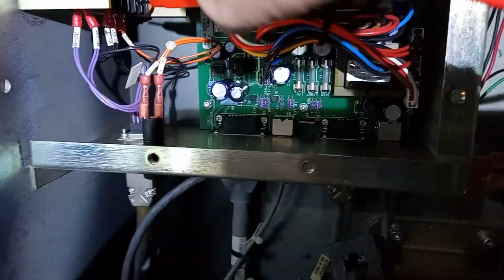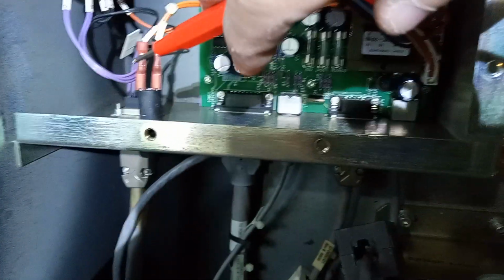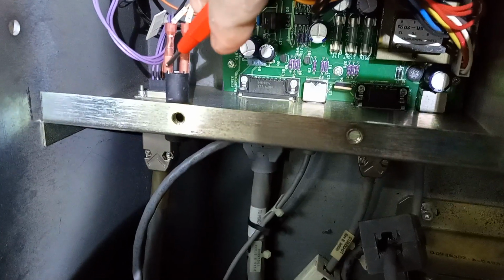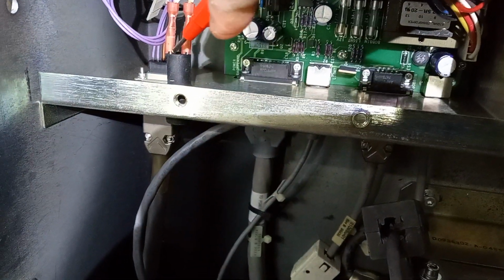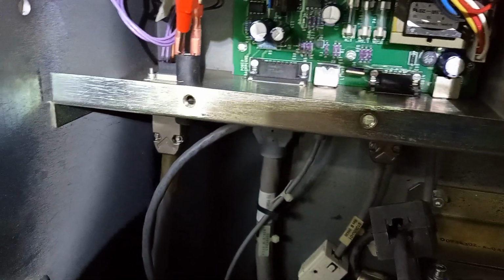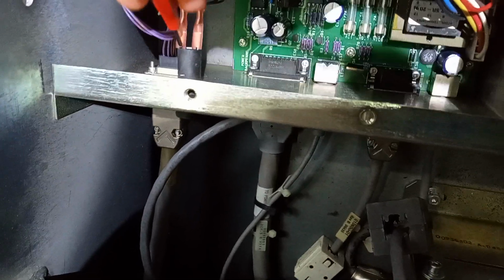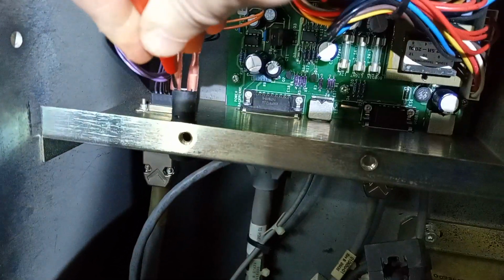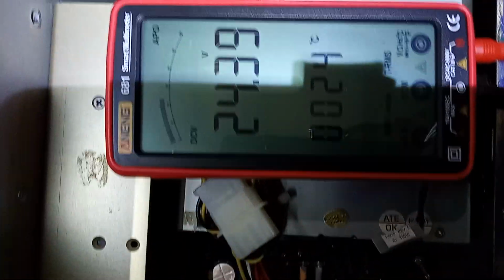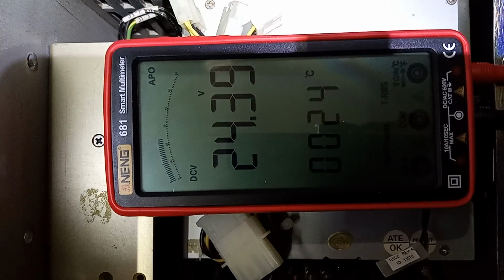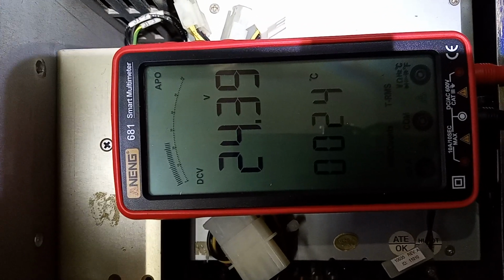Okay, you could also measure it from the top right here, which there's a fuse. If you get in here, any of these two, you should be able to probe there, and it should give you 24 volts. There it is, 24 volts. 24.39, 24.40. It's what I have this one set at.